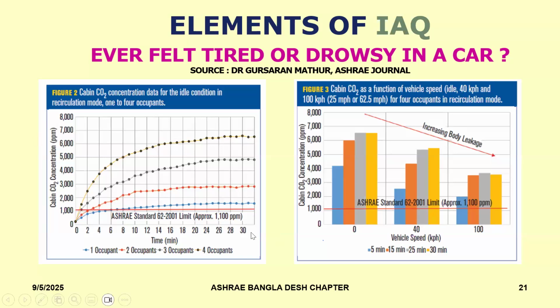Now, it's not just sufficient to say 6,000 ppm is a lot. If you look at the ASHRAE 62 limit, approximately 1,000 ppm as an acceptable limit, then you can see we are way beyond that. But it's also important to note that if you have 4 people sitting in that automobile, no matter how large it is, what is the percentage of air breathed out by one person that is being breathed in by another person, right? So that is really how you have to start worrying about spread of infection.